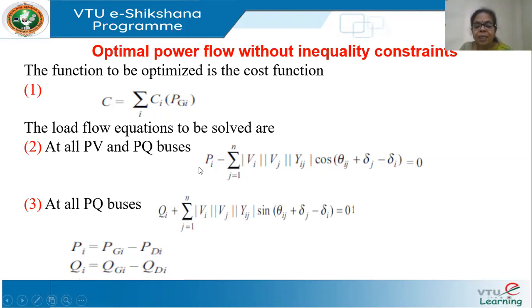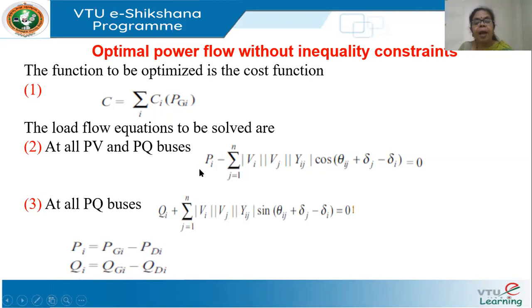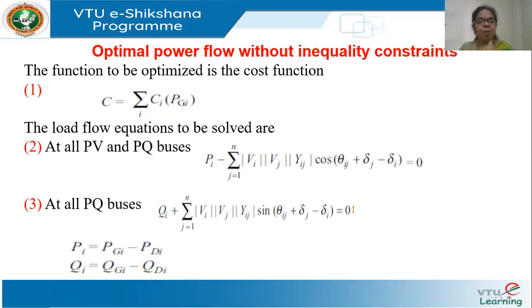The load flow equations to be solved — at all PV and PQ buses, this equation must be satisfied. The injected power PI is calculated from the given values of generation and demand: PI = PGi minus PDi. Similarly, the injected reactive power is QGi minus QDi. PI is calculated from data, and the other term is what I get as an estimate. PI minus this term should equal zero, and since P is specified at all PQ and PV buses, this must be satisfied at all buses except the slack bus.